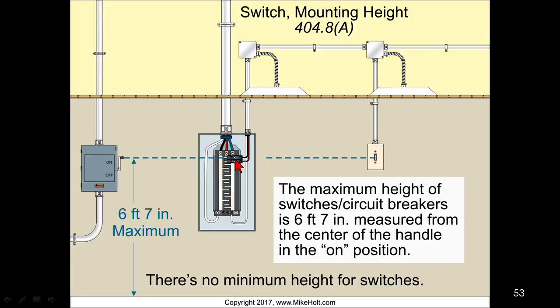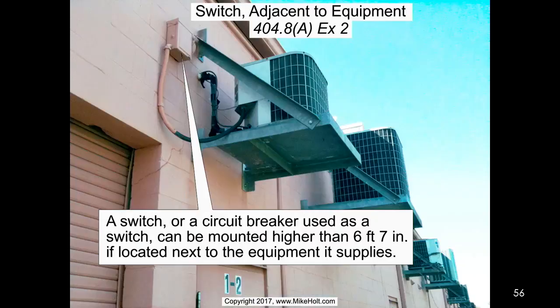I don't think it belongs in this catch-all that all switches have to be no higher than 6 foot 7 inches. If you don't want the circuit breaker higher than 6 foot 7 inches because it needs to be readily accessible, then I think we need to take this text and place it in the rules for overcurrent devices in 240, and in motors and air conditioning and refrigeration equipment. Where the height is a factor, it should be applicable, not this broad rule. Even though I want to do something that's not a disconnect, I want my light to be controlled from a high location. Okay, brilliant. Thank you. Got learned on that one.